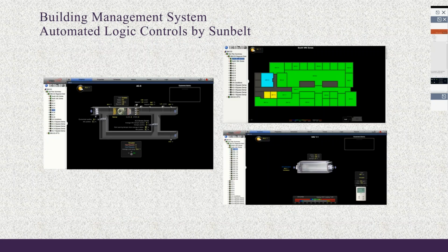The BMS system was upgraded to newer hardware and programming of advanced algorithms. By employing CO2 and occupancy strategies during scheduled building operating times, we're keeping the spaces at set points when occupied, and when the spaces are vacant, the set points are relaxed to save energy from unneeded cooling and heating until the spaces are occupied again.